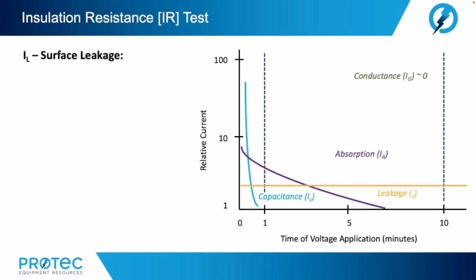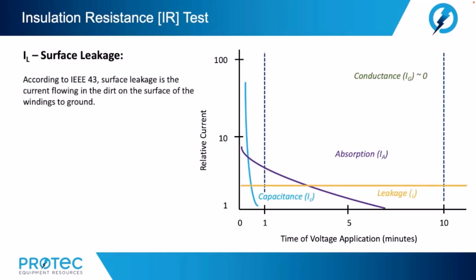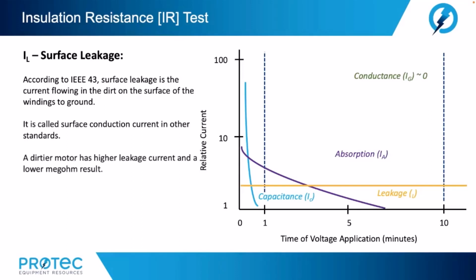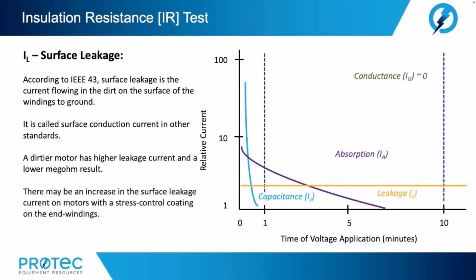But now let's focus on surface leakage. According to IEEE 43, surface leakage is the current flowing in the dirt on the surface of the windings to ground. It is called surface conduction current in other standards. A dirtier motor has higher leakage current and a lower megohm result. There may be an increase in the surface leakage current on motors with a stress control coating on the end windings.